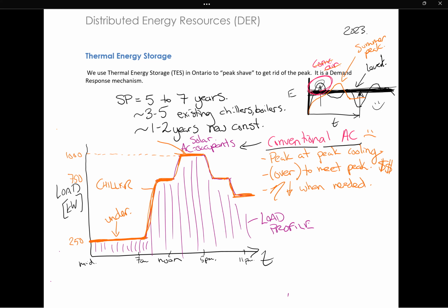This is underutilized, and this is at capacity. When it is at its capacity, it is operating with the least efficiency sometimes — it depends on the curve. But here our peak chiller load is 1000 kilowatts. That's a big chiller I had to buy, but most of the time I'm running it under capacity — I still had to buy that.